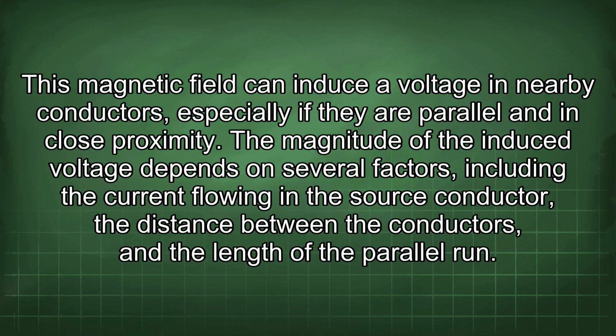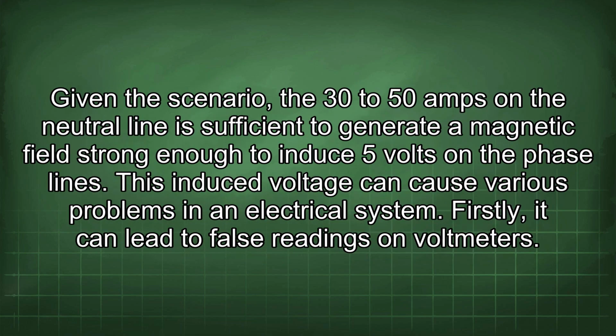The magnitude of the induced voltage depends on several factors, including the current flowing in the source conductor, the distance between the conductors, and the length of the parallel run. Given the scenario, the 30 to 50 amps on the neutral line is sufficient to generate a magnetic field strong enough to induce 5 volts on the phase lines. This induced voltage can cause various problems in an electrical system.